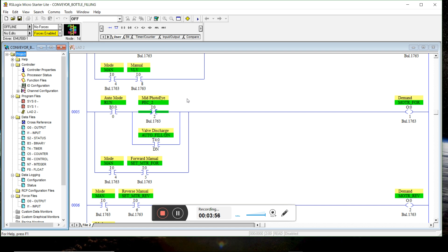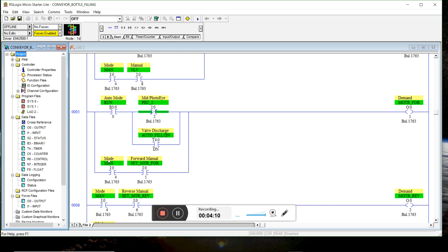Motor forward and motor reverse. For motor reverse, we can only reverse the motor in manual mode and we press the momentary push button. For motor forward, that can happen both in auto and manual mode. In manual mode, we press the momentary push button.